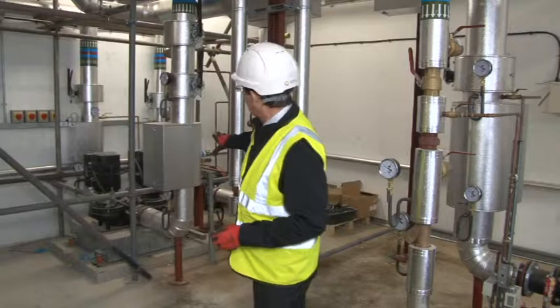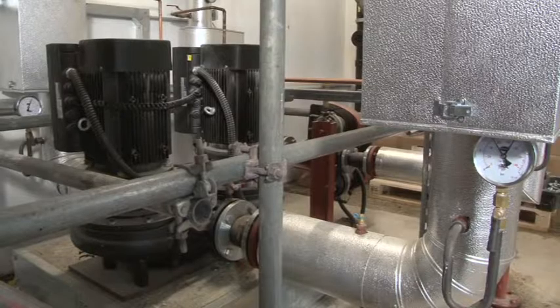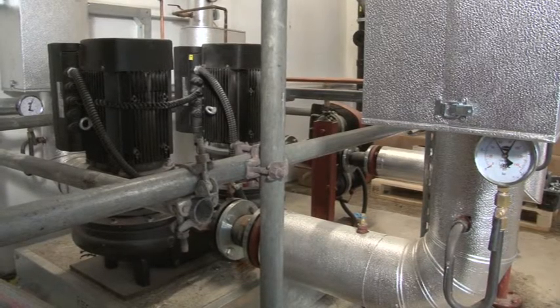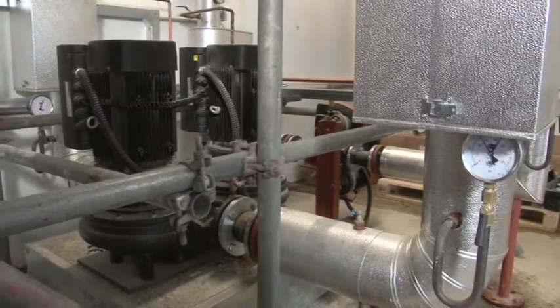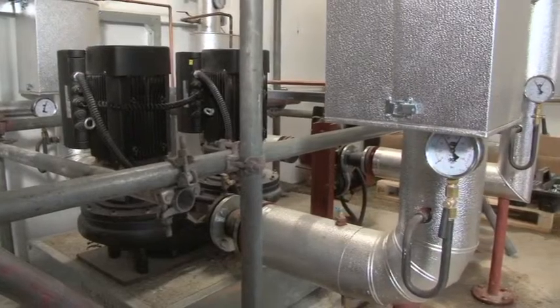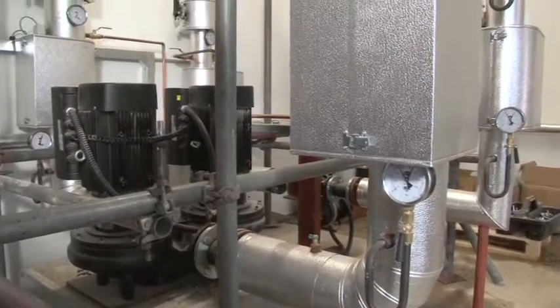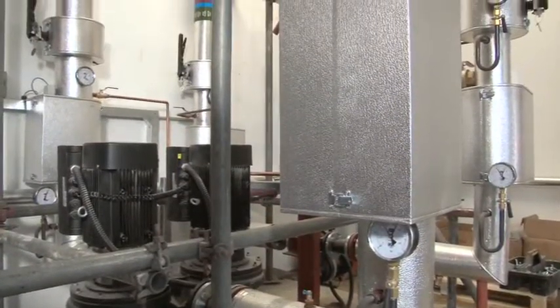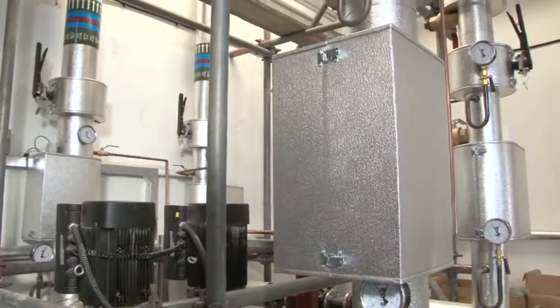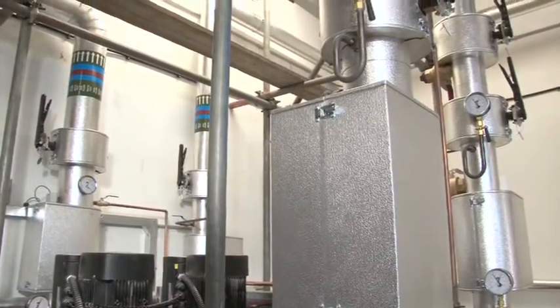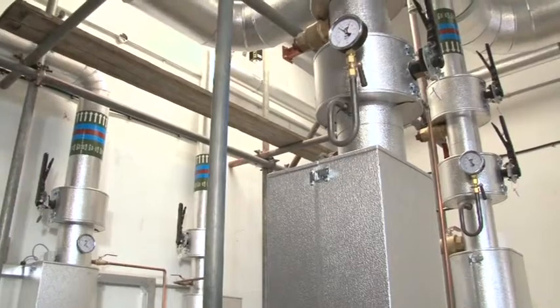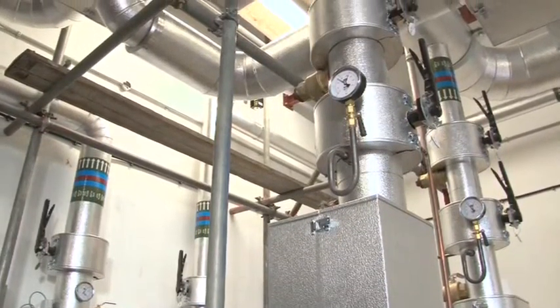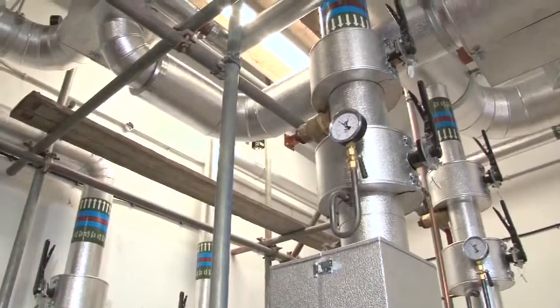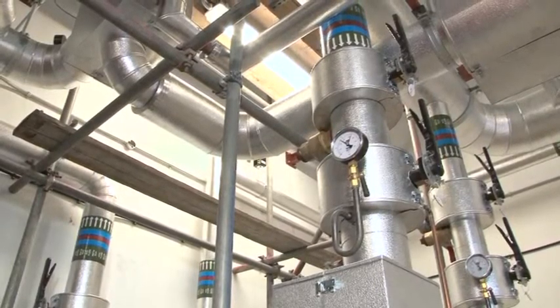The two sets of pumps on the far side, as I said, the large set are pulling the heat out of the headers and off up to the risers around the heating systems and off to the flats. The smaller set of pumps to the far side there are pulling the heat out of the headers and feeding it round to the plate heat exchanger for the ASDA side of things. Okay. So those are not operational at the moment, whereas the ones for the residential area are very much underway and operating now.